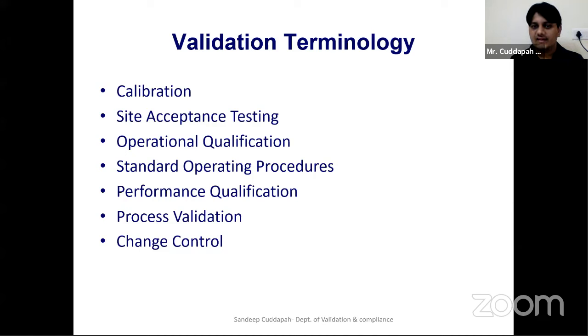So in validation, the key criterion and main thing is calibration. Why is calibration so important? Because when you are doing validation, you will have some master equipment or testing equipment to verify that your equipment is working fine. Suppose you have a heating bath. You keep a thermometer to see whether the temperature is achieved or not. The thermometer is considered master equipment or testing equipment used for validating your heating bath. If you don't calibrate that thermometer, it will give wrong results, and you will think your validation is a failure.